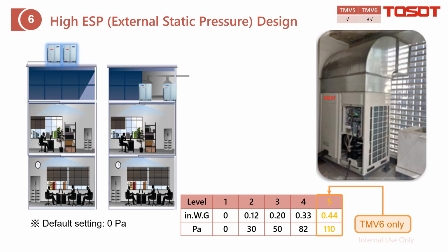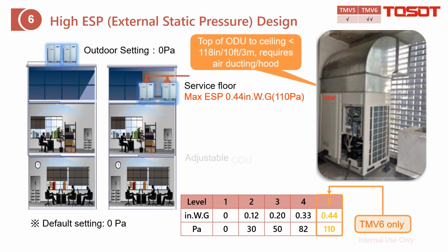For the outdoor unit, you can choose to put them on the rooftop like this, and you can also put them in the service floor. If the distance from the top of the outdoor unit to the ceiling is less than 118 inches, you need to apply this air ducting to ensure ventilation. Besides, you can also set the ESP on the outdoor unit. For GMV6, we offer you up to 5 grades of ESP setting, max up to 0.44 inch water gauge.